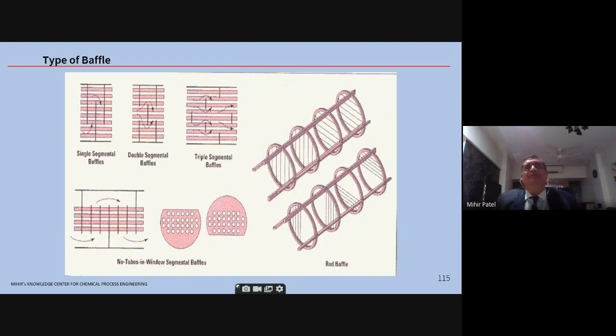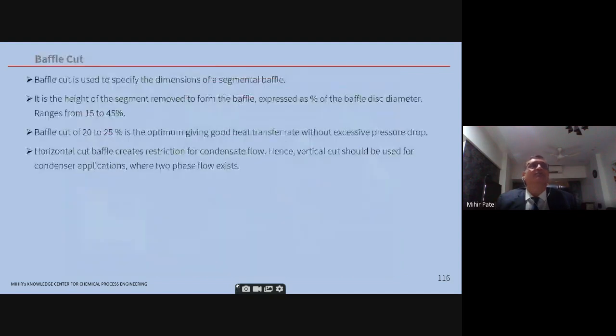But 90% you probably will go with a segmental baffles, or at best a NTIW, which is for vibrational problems. Baffle cut. A baffle cut we will come to is normally kept around 15 to 45% maximum, with 20 to 25 being the optimum. Okay.